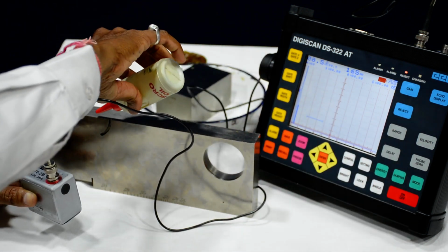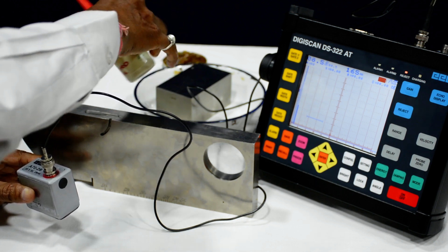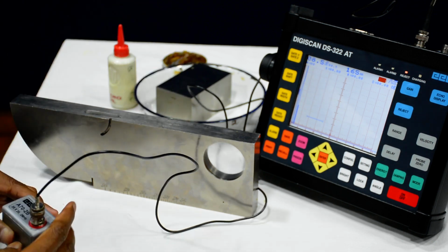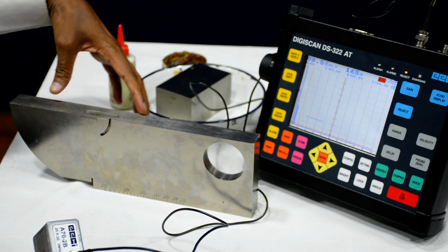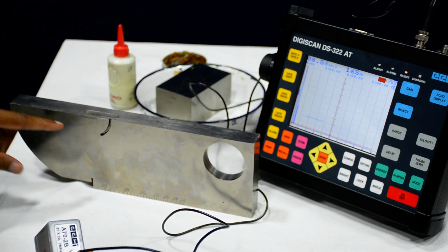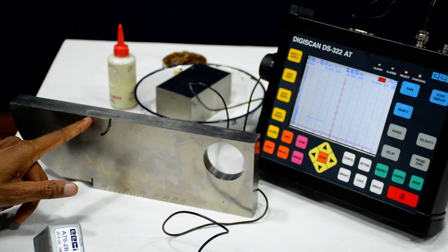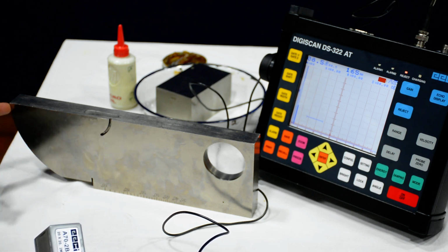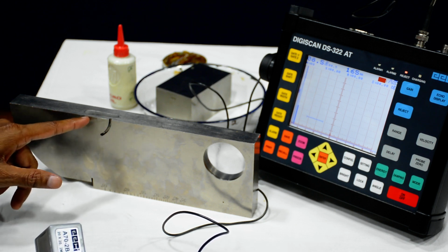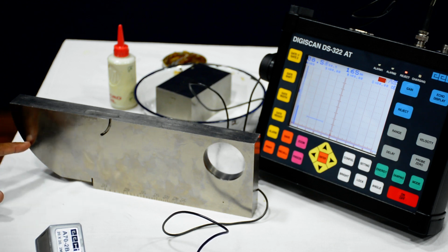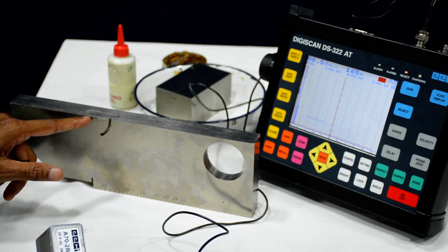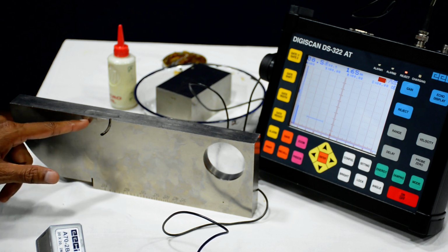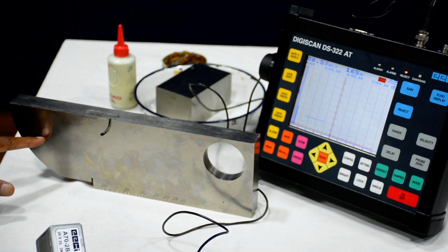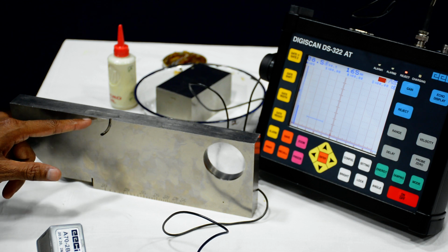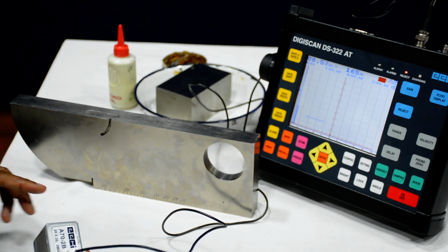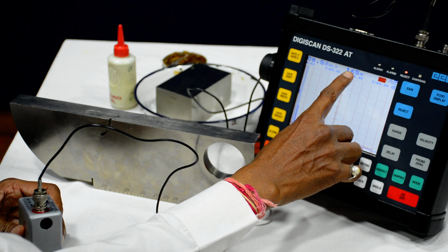For this calibration of the angular probe, we have to do the setting on this IIW block. So this is the center and this arc is radius from this center to this arc is 100. So we are sending the pulse from this location to this arc. So beam path will be the 100. Here we have to make the echo at the 100, that is the calibration. So we have taken the range 165.